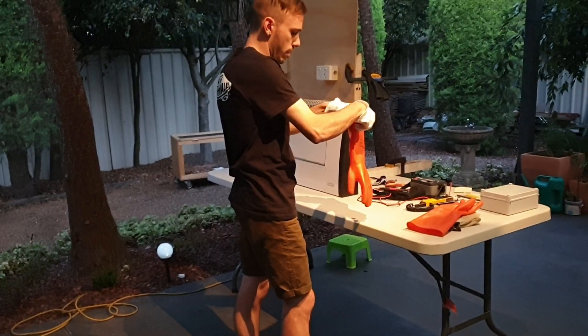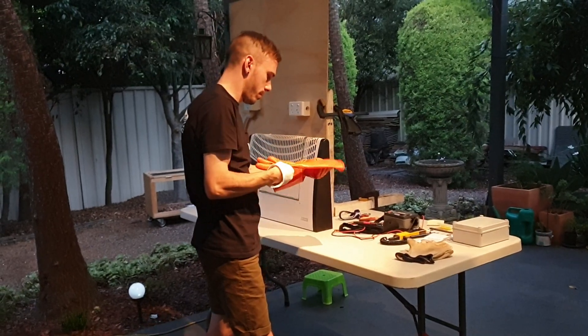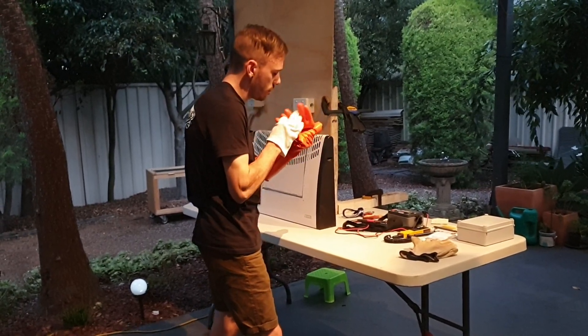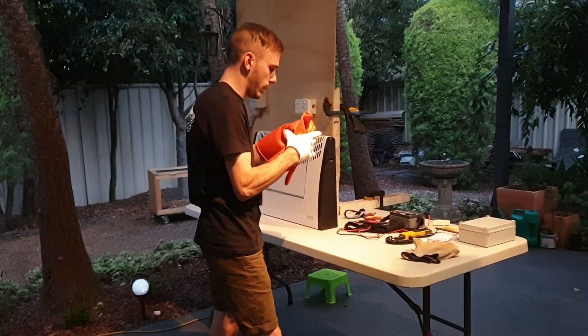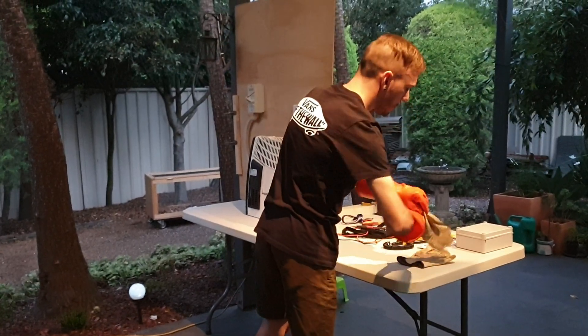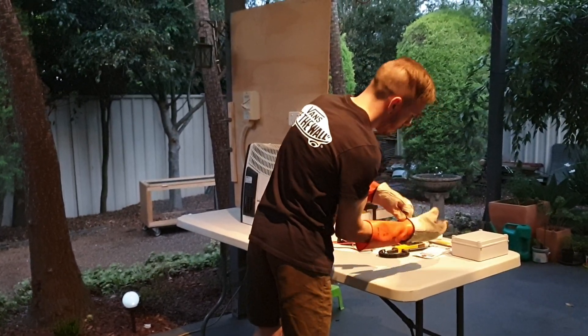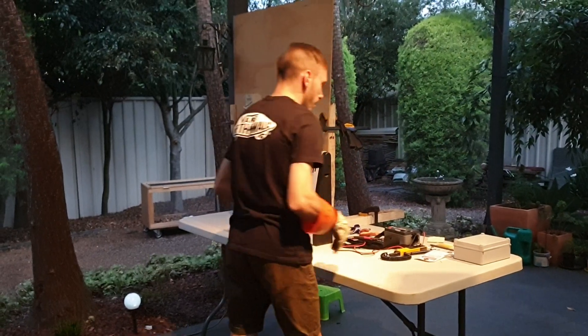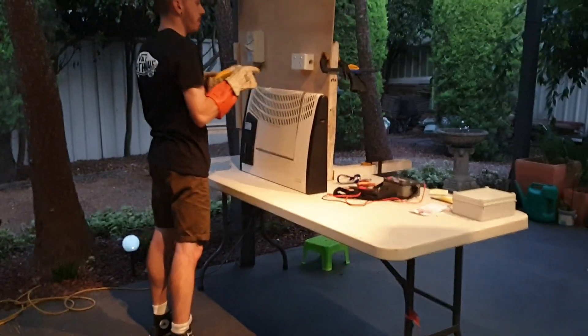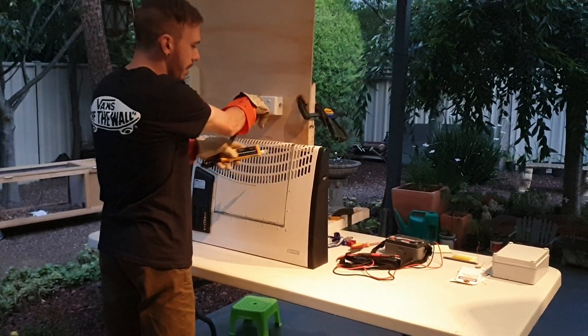That looks alright. We're going to put our final layer on, which is our guard gloves. The first test we're going to perform is testing our voltage tester. Make sure you don't touch the frame of the appliance. We have voltage at the live source and the neutral source.